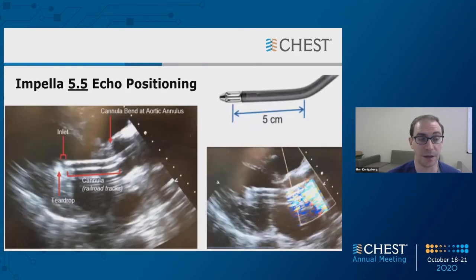I'll also make a comment here about the Impella 5.5, as the positioning for this device is different than the other Impella options. The distinction is that the cannula itself is longer for the Impella 5.5, from the bend in the cannula to the mid-inlet. And as you can see, while there is a teardrop as well, there is no pigtail catheter for the Impella 5.5. However, just like other Impella devices, we can continue to interpret the echogenic parallel lines, or the cannula railroad tracks, ending in that echolucent inlet port, followed by the echobright teardrop, as well as the color Doppler motor artifact.